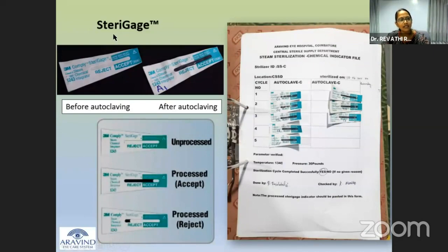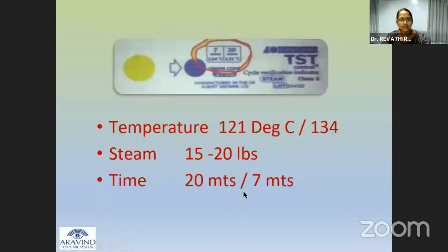The class 5 indicator, the SteriGage, has a very major role. It's very crucial. It has to be documented. Here the color change has to be complete, from an empty white to wholly black. If it continuously fails, then the batch has to be changed. Specifically, every load has to have a SteriGage.